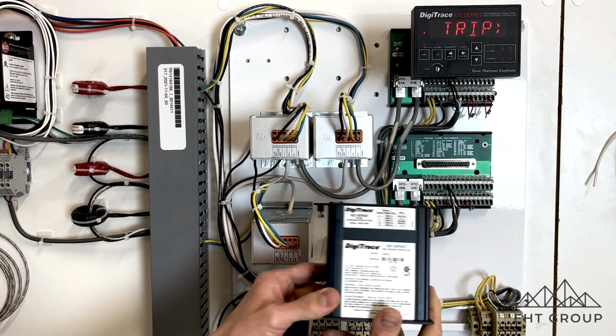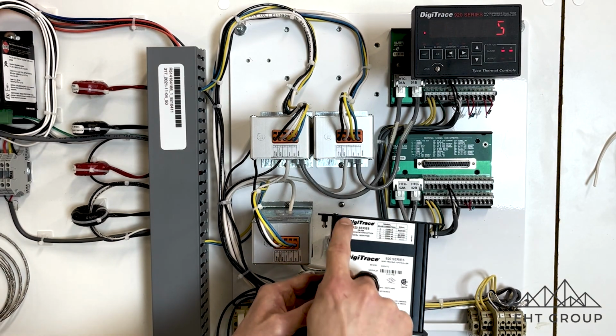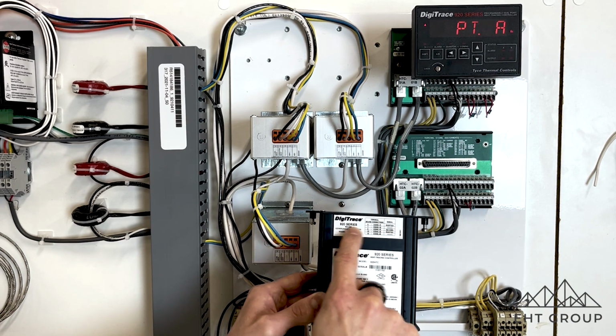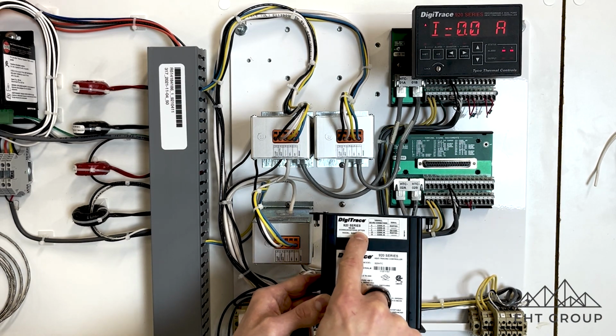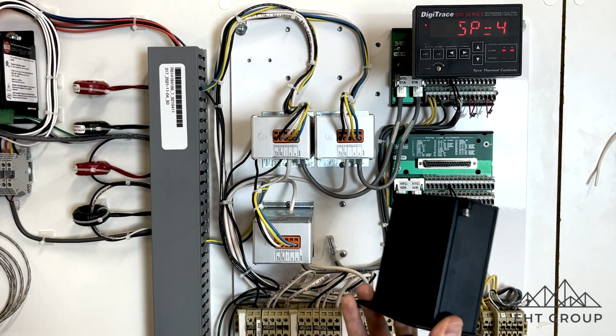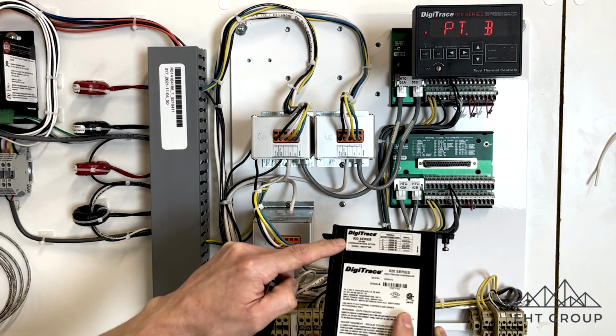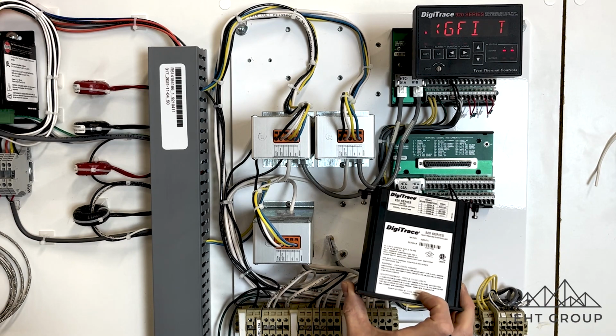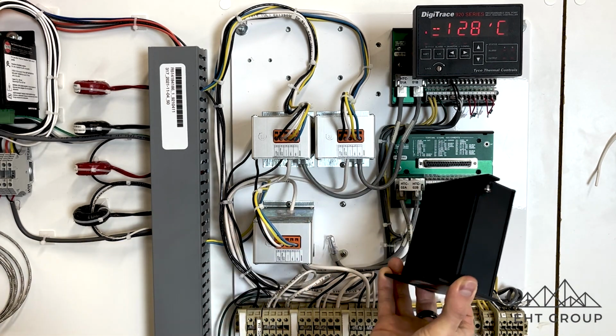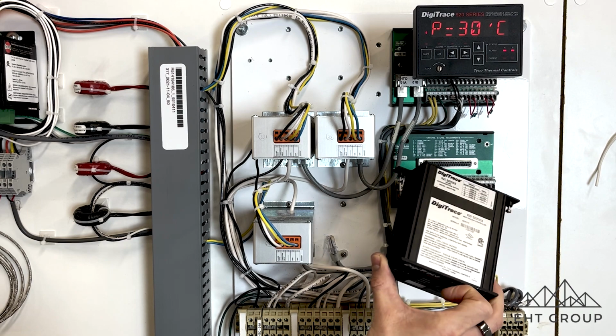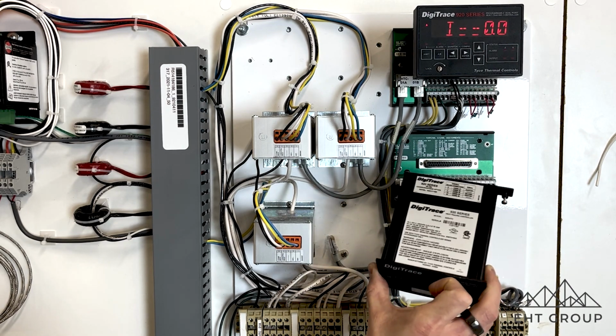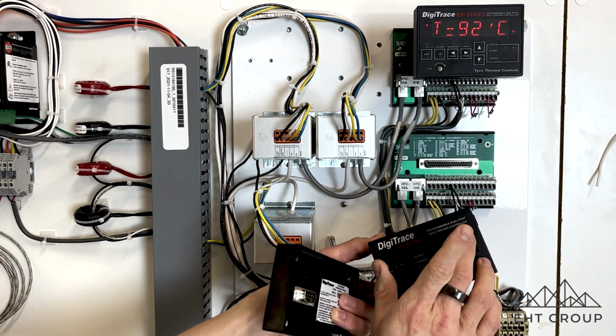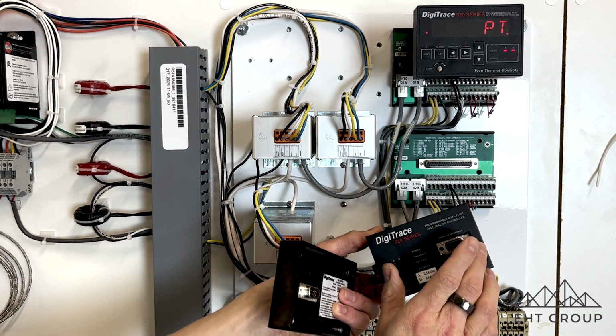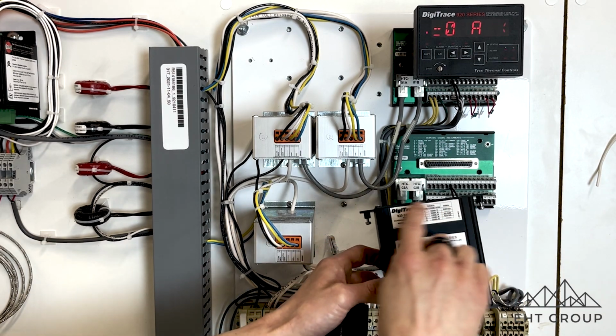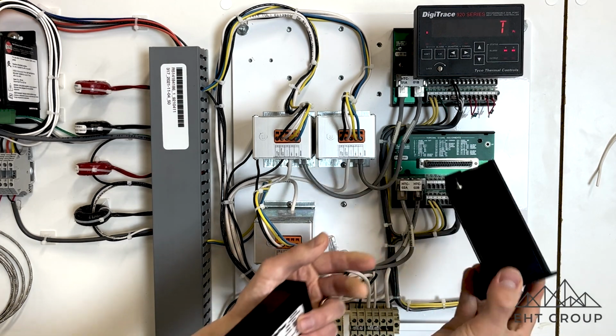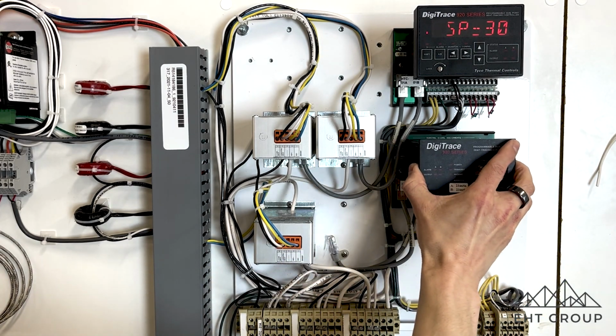The way that you tell on your controllers is this top sticker right here, and it actually tells you 920 series RS-485 communications option. So if you're ordering a 920 controller, make sure you get it with that RS-485 communication option included. That's how you tell if your module is RS-485 compatible. I'm not sure if nVent still does it, but if you had older 920 controllers, some of the versions will allow you to upgrade if you get the chips, but I'm not too sure if nVent still offers that as an option.